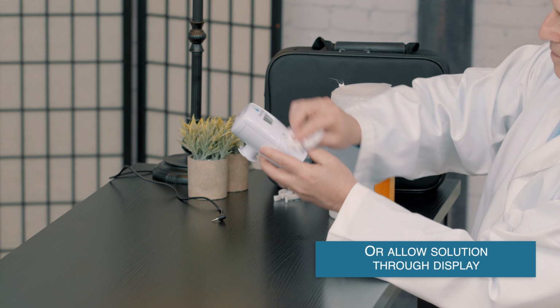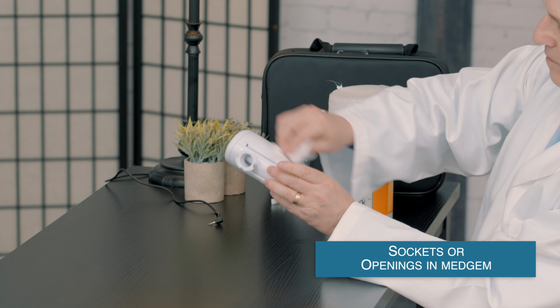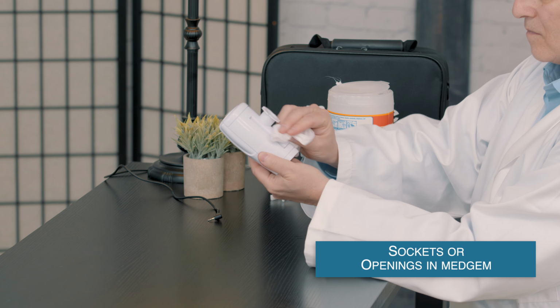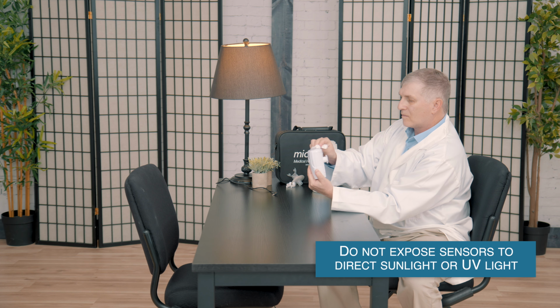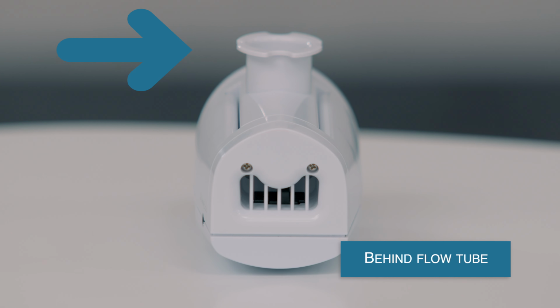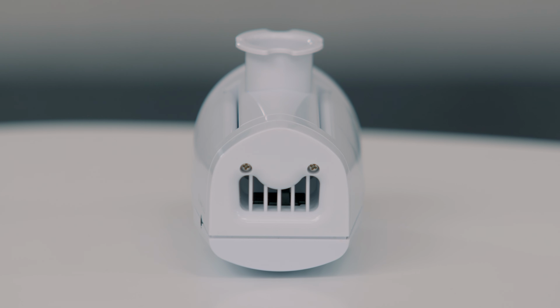To maintain your MedGem device, regular cleaning with recommended materials is essential for its longevity. Do not submerge the device in water or allow any solution to penetrate the display window, sockets, or openings in the product. Do not expose the device O2 sensors to direct sunlight or UV light. The O2 sensors are located behind the flow tube and are exposed when the flow tube is removed.